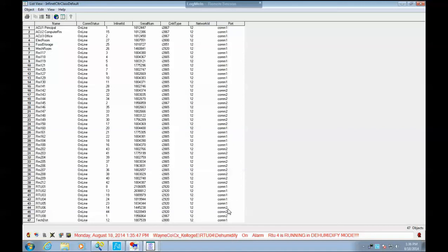So that would allow you to determine whether it's a COM port only problem or not. It could be everything on COM 1 is down. So either way, one is up and one is down. Your main net controller, which is the main brains, is working, but one of your COM ports is bad. So then again, you're going to have to go to the field and diagnose which controller or what's the problem with the COM port.